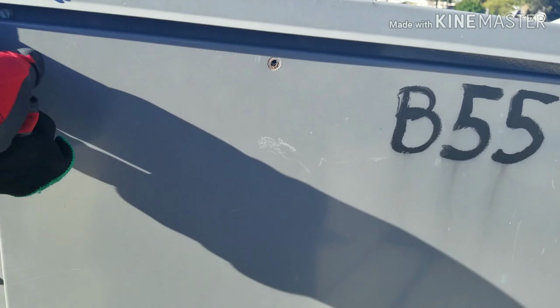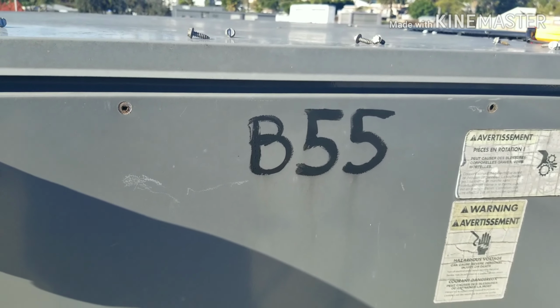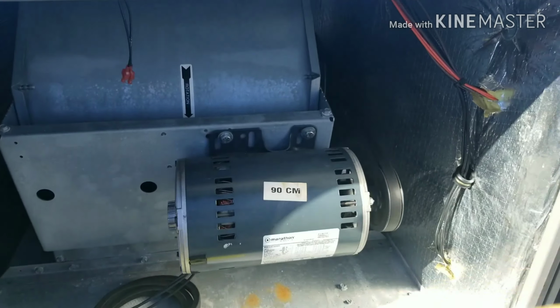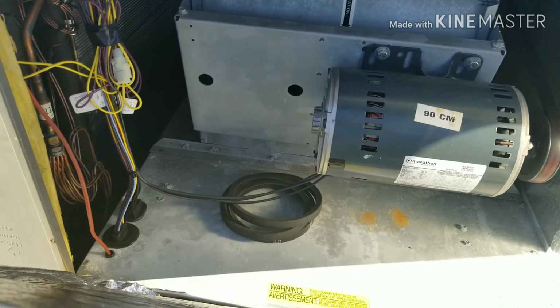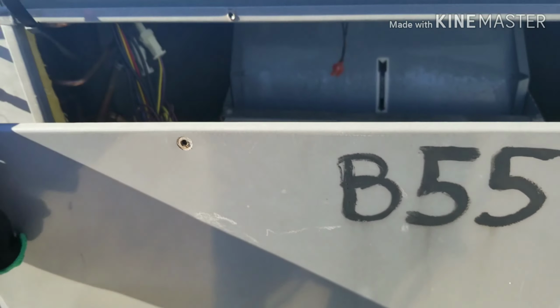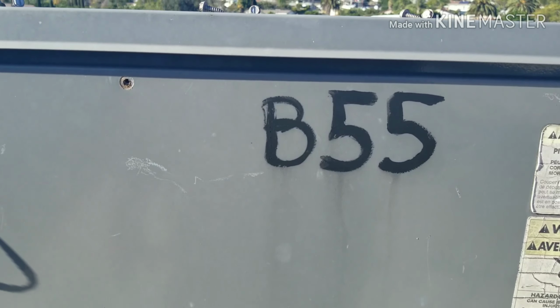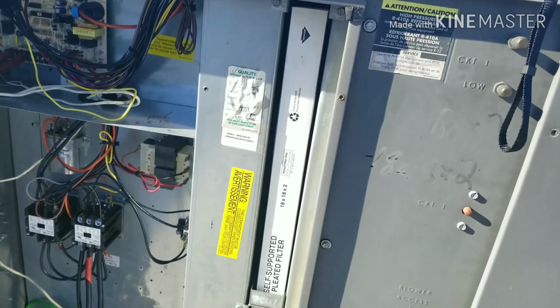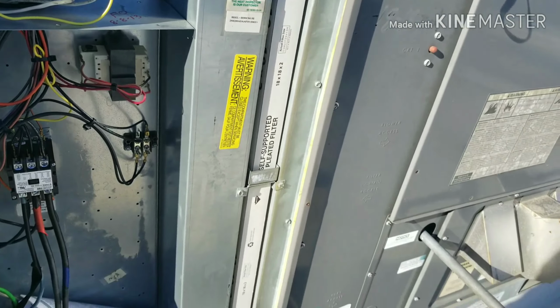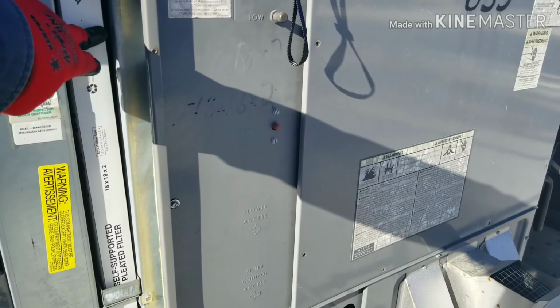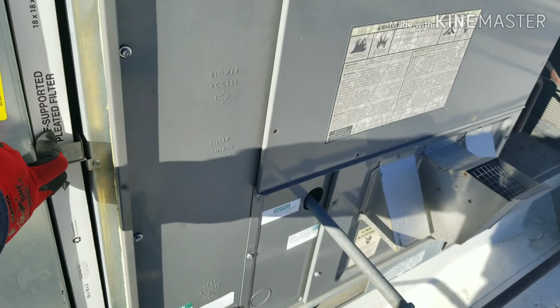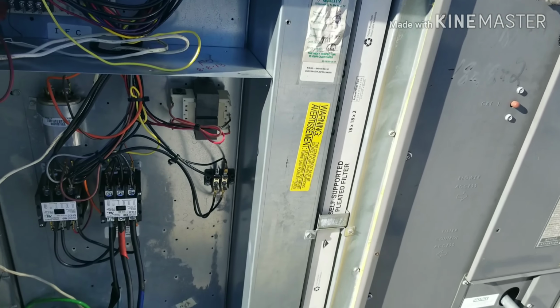Fan's running. So it has a B55 belt. I usually put an extra belt in there just in case. And so that's not making any sound. Sounds good. The whistling sound you hear is the air coming through here, through the tight spot, through the filter bank.